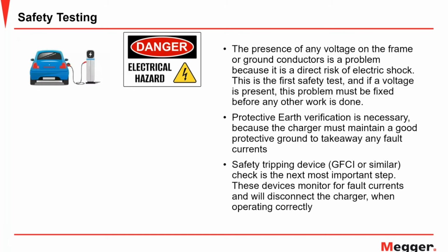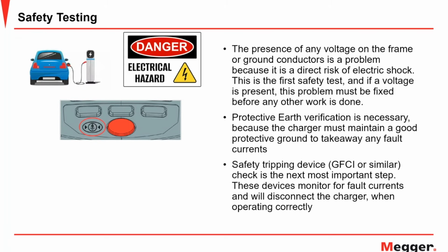So, safety testing. The very first thing is making sure there's no presence of voltage in the frame or in the charge point itself, at a point where a user or someone can come and touch it and feel that voltage. In a lot of our equipment, and equipment from other manufacturers, there's a symbol where the user is the reference point, with a lot of safety in between - you put your thumb or finger on there, and connect to whatever you're testing, in this case the charge point, with PPE on, just in case there's a hazardous voltage. If you touch that, the instrument itself will see if there's a voltage difference between you and the frame and connection of that unit.